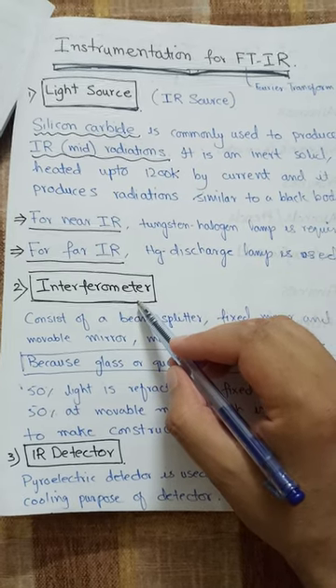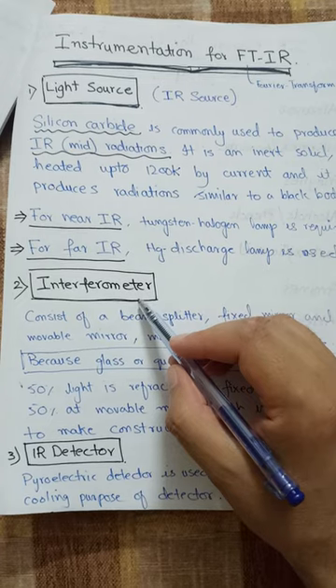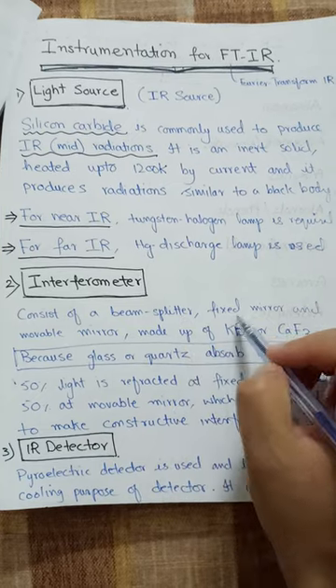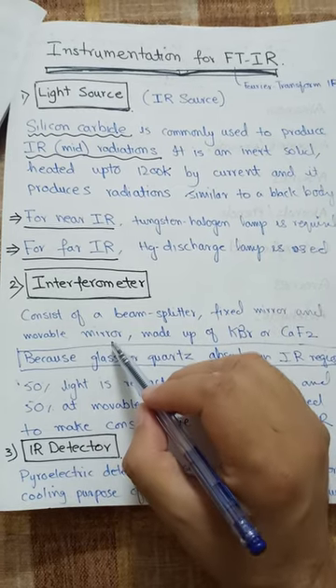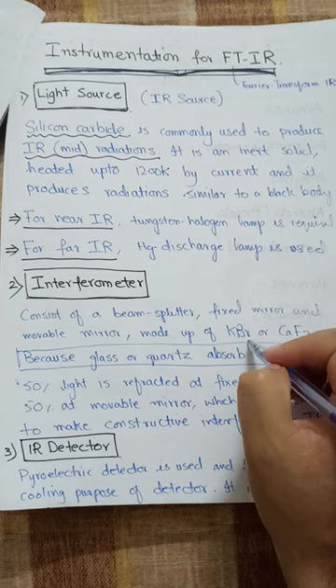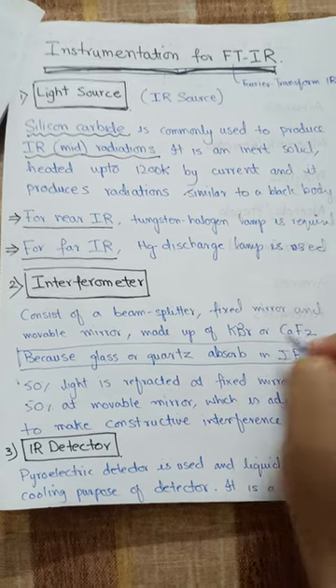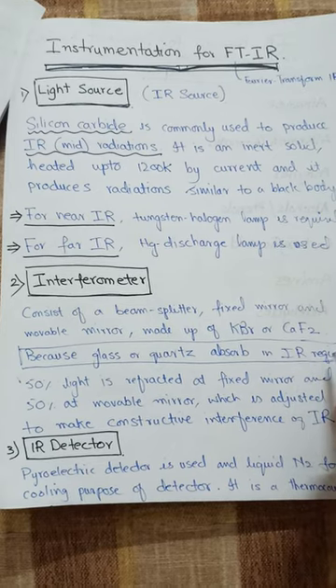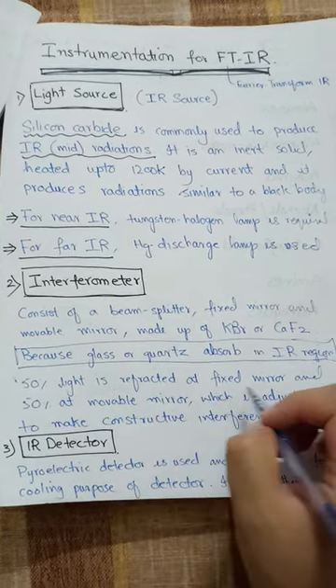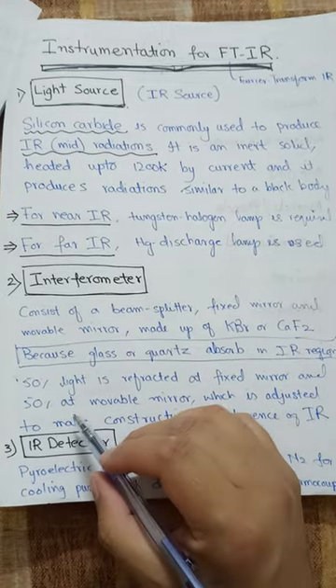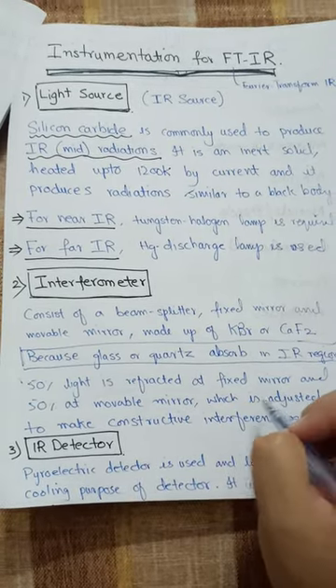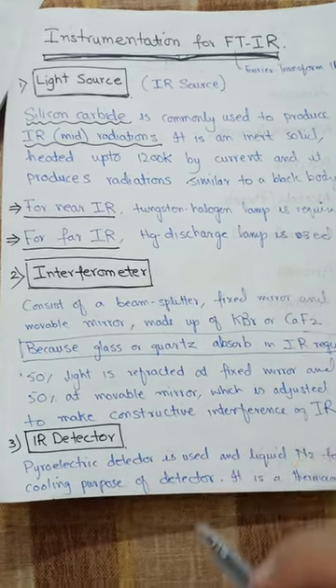The interferometer is used to make constructive interference of the IR radiation. It consists of a beam splitter, a fixed mirror, and a movable mirror. These are made of potassium bromide or calcium fluoride, because glass or quartz absorbs IR radiation. Fifty percent of the light is reflected at the fixed mirror and 50% at the movable mirror, which is adjusted so that constructive interference is produced.